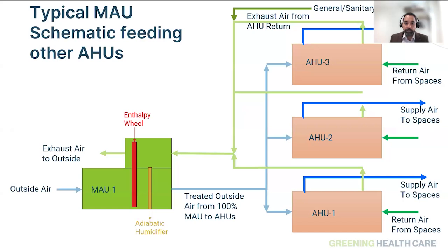One of the things that usually comes up in discussions around existing mechanical rooms is, how can we retrofit an existing AHU with an enthalpy wheel or with an adiabatic system if we don't have the space? We're trying to put this idea out that there might be possible solutions that are outside the box currently around these systems. Generally, in a mechanical space, you have an exhaust on one side, an intake on the other side, and then you have AHU systems lined up with those plenums. And yes, it's possible that you may not have space to retrofit an existing unit with an enthalpy wheel.